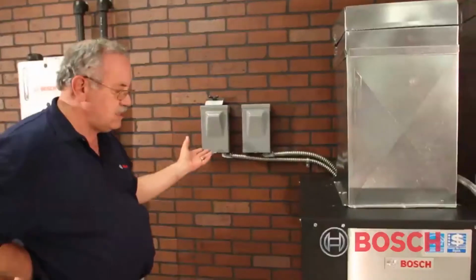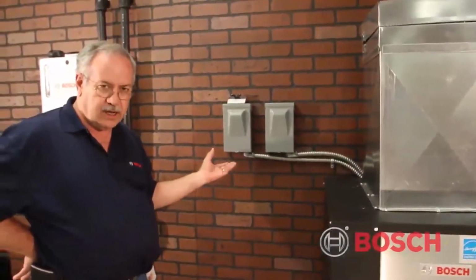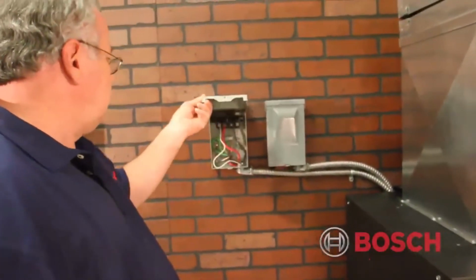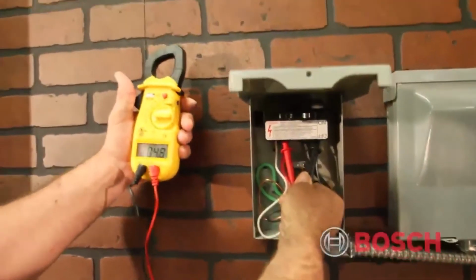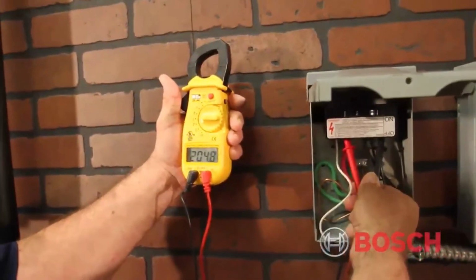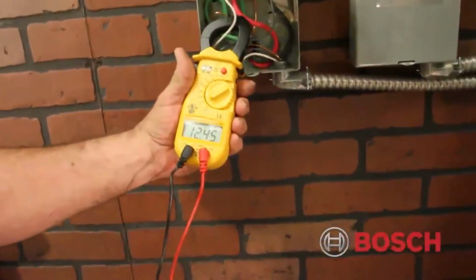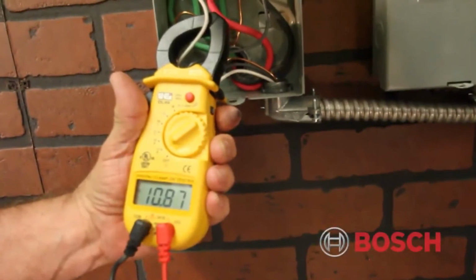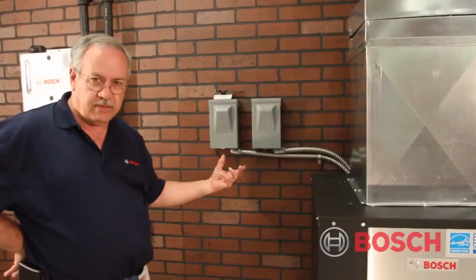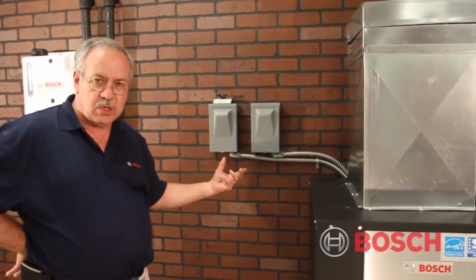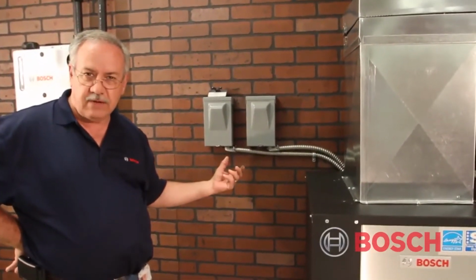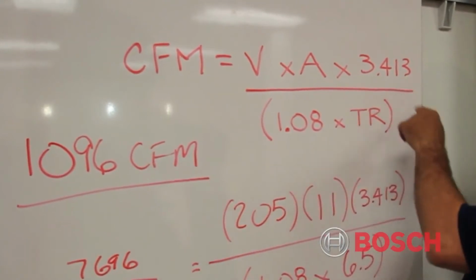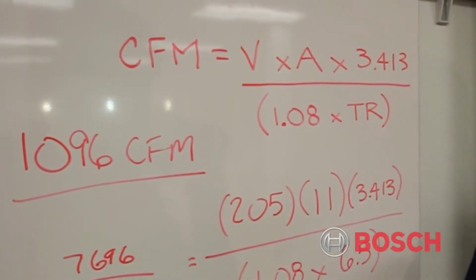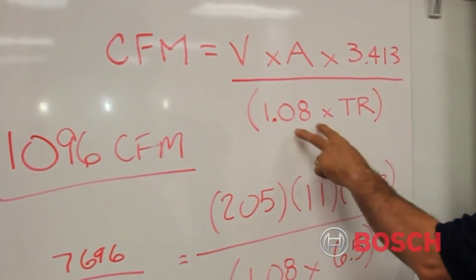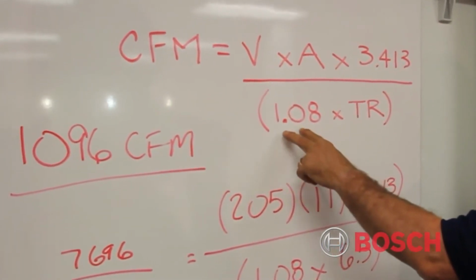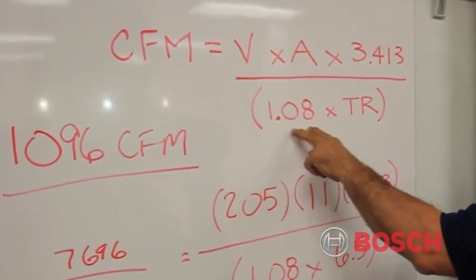Then I'll go to the heater disconnect, open it up, and remove the panel. I will take a voltmeter and measure voltage across L1 and L2 while the heater is energized. Then I will take the ammeter and measure around one of the wires, black or white typically, to get the amp draw of that particular heater while it's running. I'll use the sensible heat formula for CFM, which is volts times amps times the conversion of 3.413 BTUs per watt, divided by a constant, in our business 1.08, times the temperature rise across the heater while it's running.